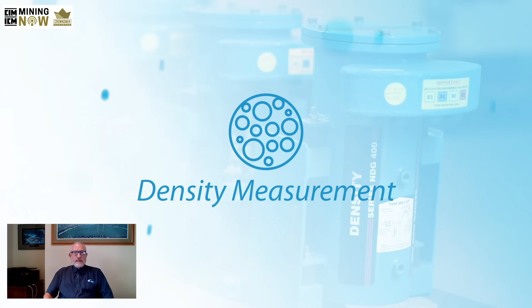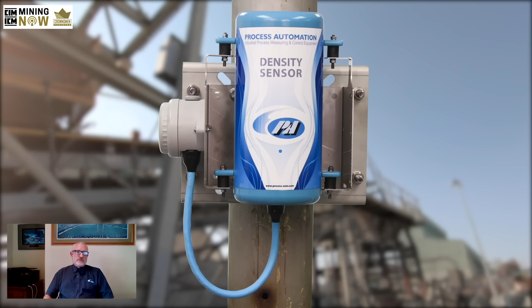So the question you're asking is from the mine's point of view: okay, so the transmitter is the same. The sensor changes. So on a density gauge, for instance, unlike a conveyor belt scale where we're measuring the tonnage, the throughput of the material on the conveyor belt, many mines have got a pumping operation. And so they might be dredging, for instance, and they need to know exactly what specific gravity the slurry is running at, because if they start dredging and they are picking up too much sand or mud, you'll choke the lines. And if they're only pumping water, that's not efficient. So they need a way to determine exactly what the specific gravity is of the slurry that they're pumping.